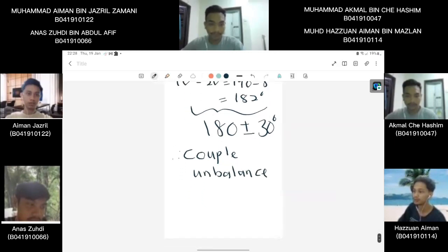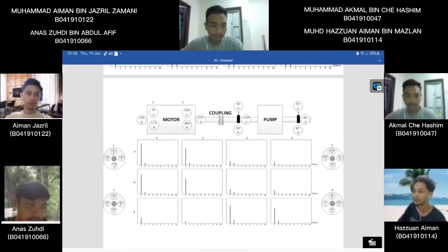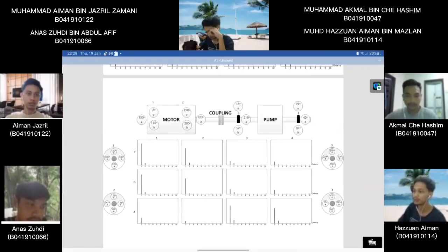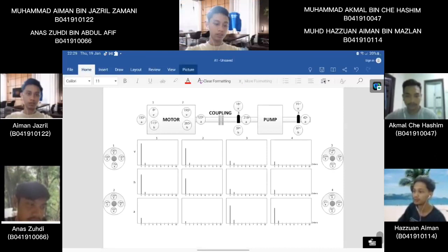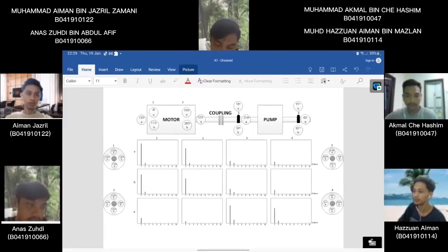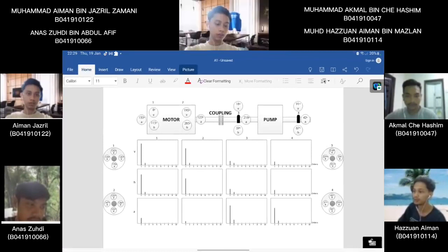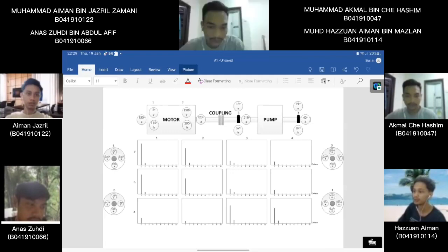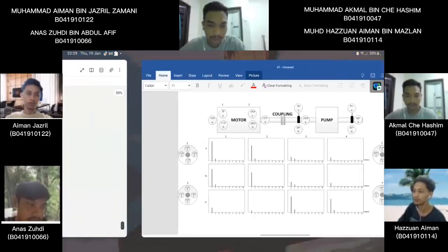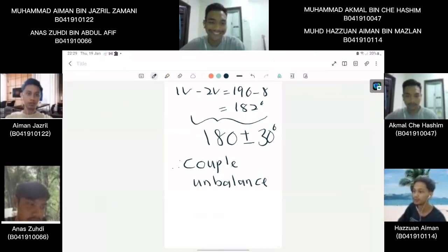Okay. So we move to the pump, position 3 and 4. What do you think, Ayman? Axial is larger than radial. Okay, axial bigger than radial, and we have 1x and 2x. What is the dominant, Akmal? It is obviously 1x, right? Right, 1x is dominant. I'm just testing you, bro.